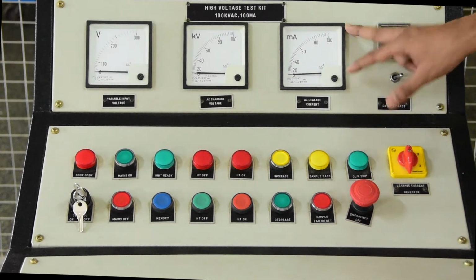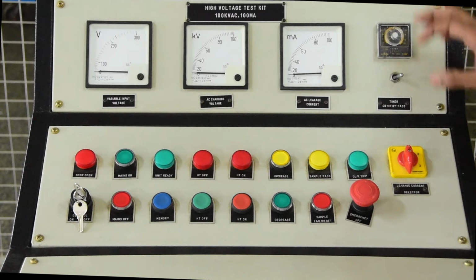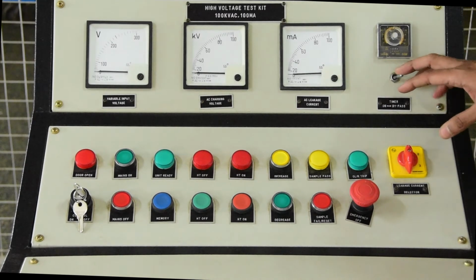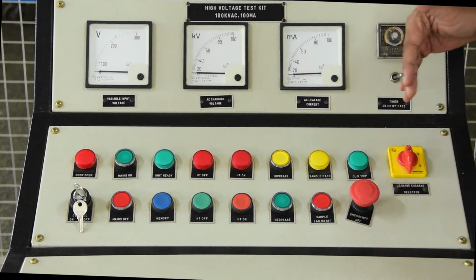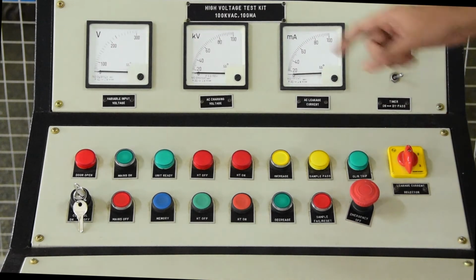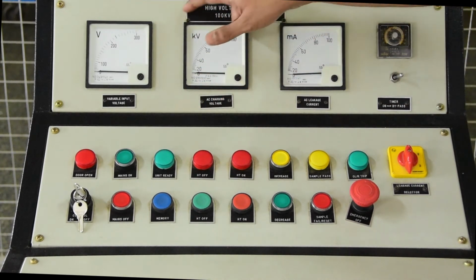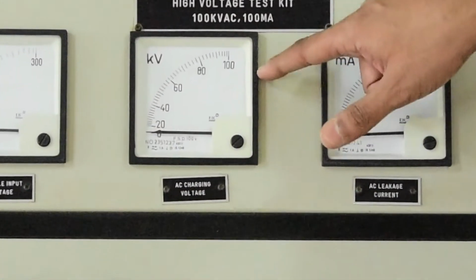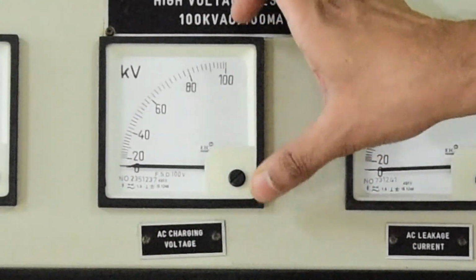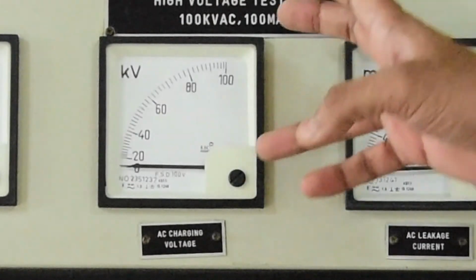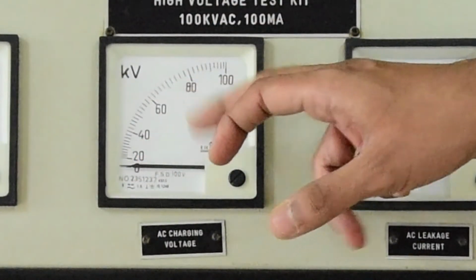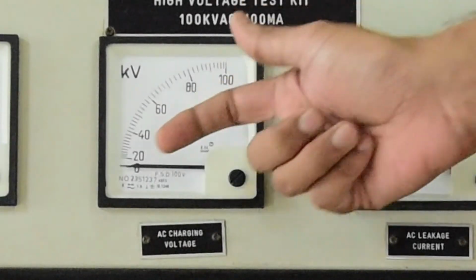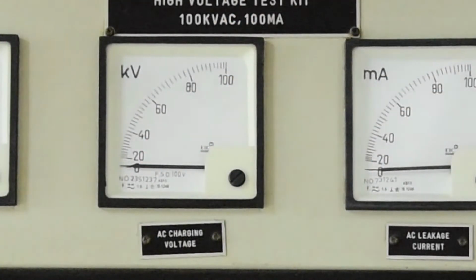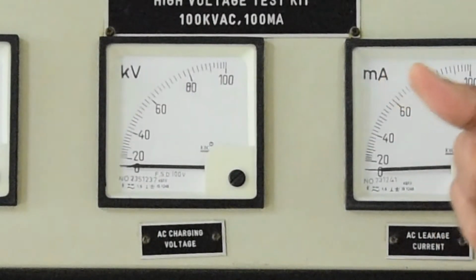And the third one is the leakage current, and this is the timer setting and the timer controller switch. For the purpose of this particular experiment of calibrating a voltmeter, our main focus will be on noting the observations shown by the charging voltage, or the output voltage of the cascade transformer, which is reflected when there is a spark over across the air gap for a set amount of spacing. We have already set the spacing to be 10 millimeter.